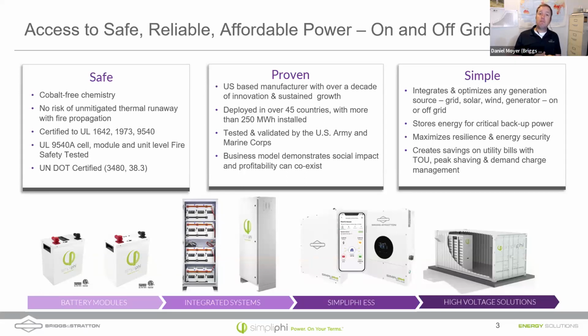We do have UL listings that prove just how safe and effective that chemistry is in our form factor: UL 1642 on the cell level, UL 1973 on the battery module level, and UL 9540 on the system level. There's also UL 9540A, the large-scale fire testing, which is not a pass-fail test. It simulates what a thermal runaway event would look like, and what happens is recorded. Spoiler alert, not much happens in our batteries. That helps inform what we call out in our 9540 UL listing. UL 9540 also looks at when you combine different components, like an inverter and a battery system, to make sure you're not introducing any unforeseen risks that might otherwise occur.